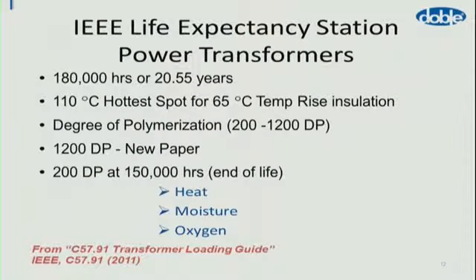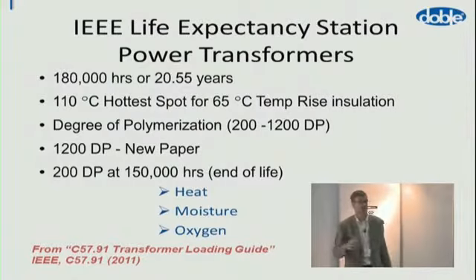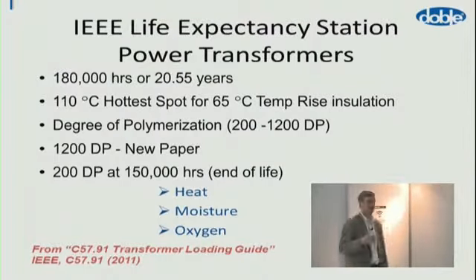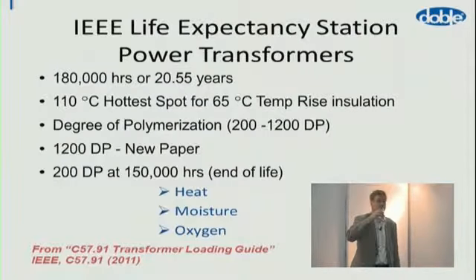This is an interesting slide. First, most transformers are not loaded to 100% of the time. Second, we're based on a hotspot calculation, and the hotspot isn't measured 100% correctly — it's measured with an estimation. So most of our calculations about the actual aging of a transformer are an estimate. We don't know the true hotspot, we don't know exactly how precise that value is, and we don't know how long it's been at that temperature. But if we have an estimate, we can then say what the degree of polymerization should be at the end of life, and how long our transformer has got left to live.